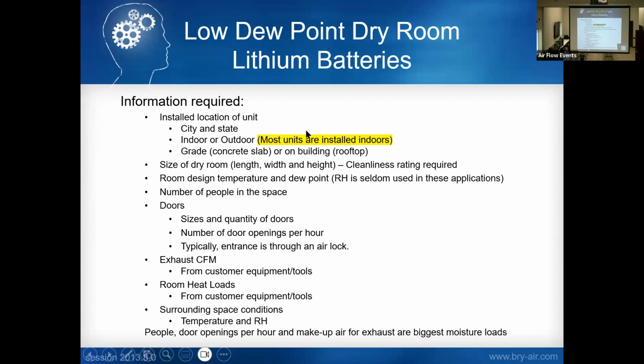There are typically no conveyors going in and out of these rooms. Everything is brought into airlocks, even the material. They build bigger airlocks for forklifts to drive into and lower 2 or 3 pallets. The high-speed roll-up door shuts down. The material stays in there 5 to 10 minutes before someone on the inside opens the inside roll-up door and pulls that material back into the space.